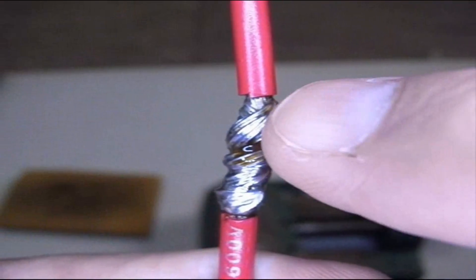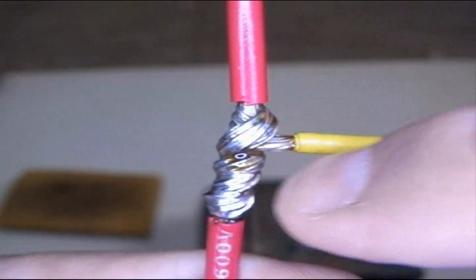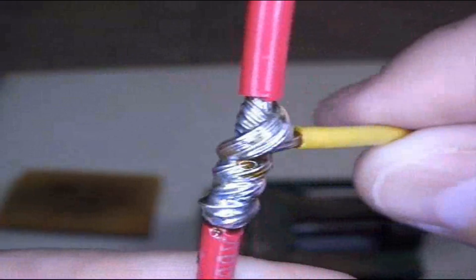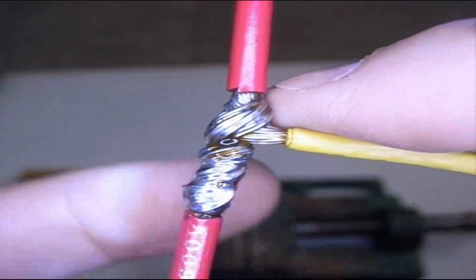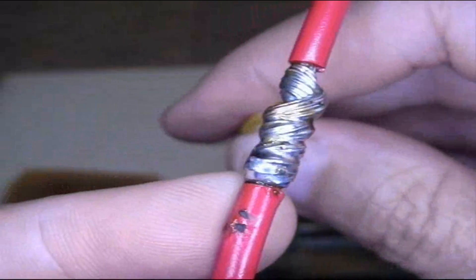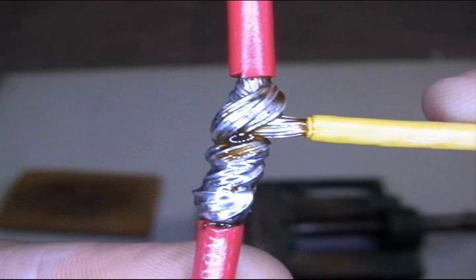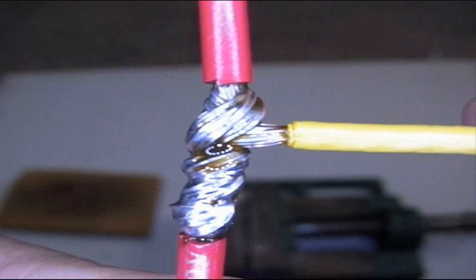Let it cool and we'll inspect it. You can see pretty clearly here our knot that we tied in there by first going up then coming back down. This is a tremendously strong joint. It does take a lot of copper, it does take a lot of solder so that's the drawback. It is rather bulgy. It's not a nice smooth inline joint that you're going to hide but it is tremendously strong. My guess is that either wire will break before that joint gives way.